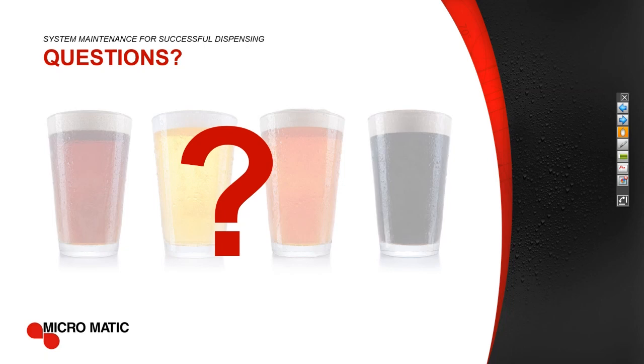So if the walk-in's working, but it's foaming at the bar and the beer's hot when pouring into the glass, then we can figure out that it's a glycol issue. If the glycol's working but the cooler's warm, we can figure these things out too. But there are a lot of issues. 90% of foaming issues are temperature related, I will put it that way. There are lots of other things that can do that. Any irritant, bad equipment, or dirty equipment can make beer foam as well. We talked briefly about FOBs, but I could talk for four days on this, so I apologize for cutting that short. Okay, last one.